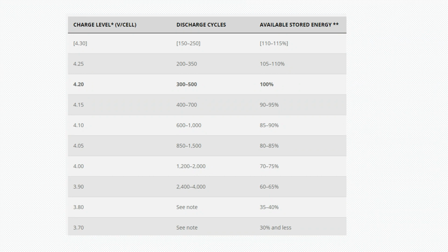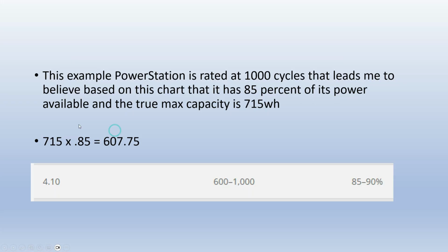With lithium cells, like 18650 cells, it's a little bit different because you're going by cell voltage. You've got 4.2 volts as the max cell voltage those 18650s go to, and then you get down to 3 to 3.5. That one is actually rated at 1,000 cycles, so it's probably more like 85% because the BMS is chopping off 15% of the battery to give you this, and it's only charging to 4.1 volts per cell.